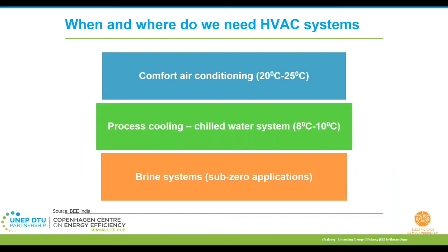Applications generally vary. If it is for comfort and space conditioning, that can be, for example, office spaces, lobbies, conference halls in buildings, shop floors, and industries. Then the systems can be used for process cooling, mostly for industrial applications, let's say maintaining bearing temperatures of a machine or equipment, maintaining reactor conditions or heat exchanger temperatures. Brine systems are generally used for critical applications where, instead of water, brine solutions are circulated. You can often see this in pharmaceutical industries.